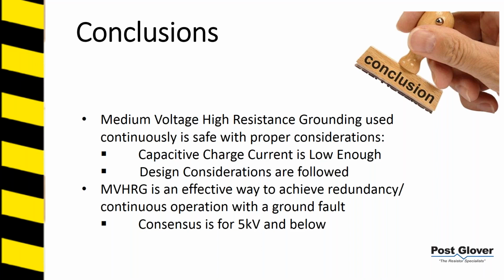And once again, I wanted to stress that the consensus for safety is for 5 kV and below. At that point, your voltage is low enough. For example, if you have 13.8 resistor, you have 10 amps ground fault current. That's a lot of wattage. There's potential for arcing potentially. So it's once again, if you don't have a comfortability with it, I would stick with that consensus.